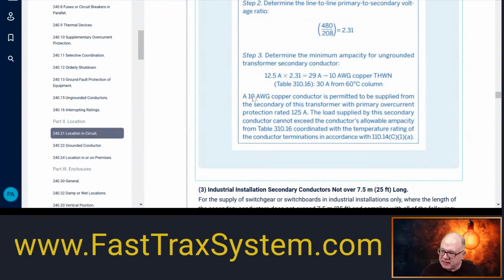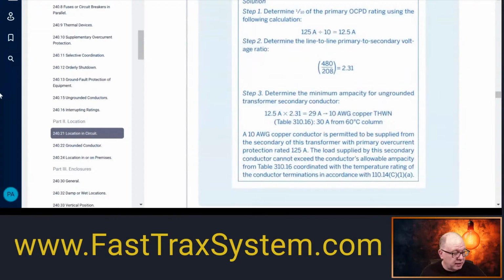Now, a 10 copper conductor is permitted to be supplied from the secondary of the transformer with primary overcurrent protection at 125 amps. The load supplied by the secondary conductor cannot exceed the conductor's allowable ampacity from 310.16, coordinated with the temperature ratings of the conductor terminated in accordance with 110.14(C)(1)(a). Okay? All that is extremely important.